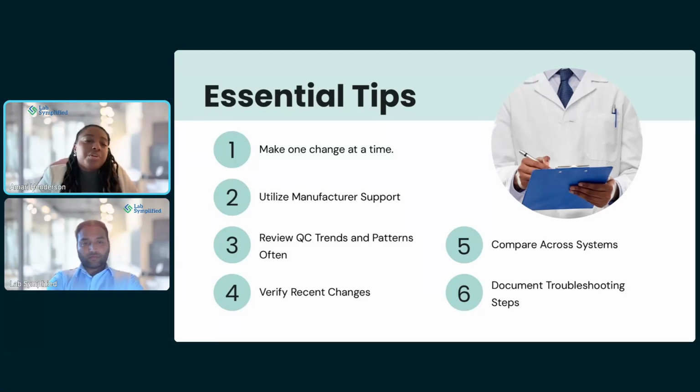Review QC trends and patterns often. A lot of times this is not an issue because you have a quality person that reviews these things, reviews your Levy-Jennings charts often so that you can catch trends before they escalate to the point where it is a major issue.